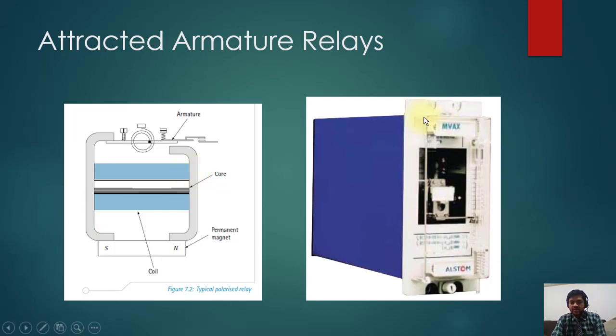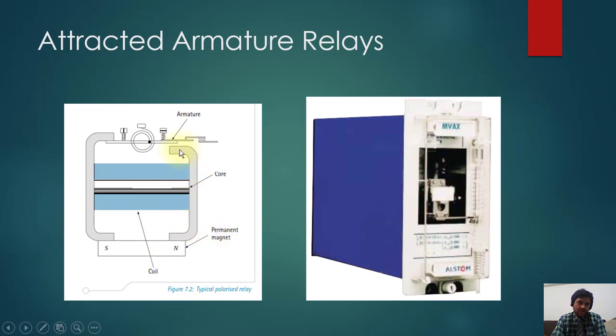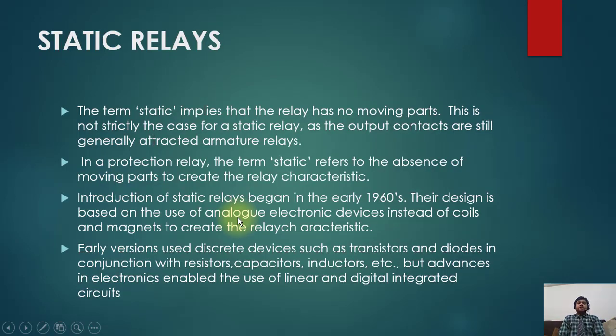This relay shown here is still in use — it is the MVAX, which is a DC supervision relay. Here you can see the core, the coil, and the permanent magnet. When the coil is energized it attracts this contact down and the electrical contact is closed.